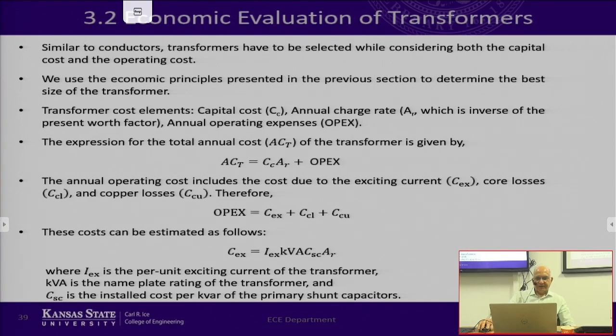So the total annual cost of a transformer is given by the capital cost multiplied by AR. In this case, what we are trying to do is convert everything to annual cost. Whatever the capital cost is, we convert it; in the previous example, we converted annual cost to present worth, but now this is the reverse of that. Because we have the fixed cost to buy the transformer, we convert it into how much is the annual cost. So this cost of the transformer is multiplied by a factor which is the reverse of the present worth factor.